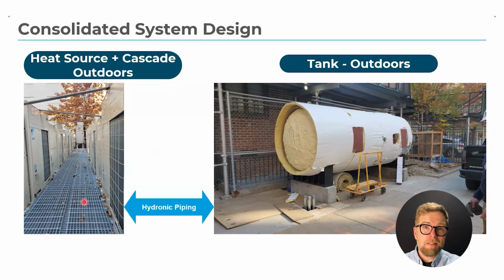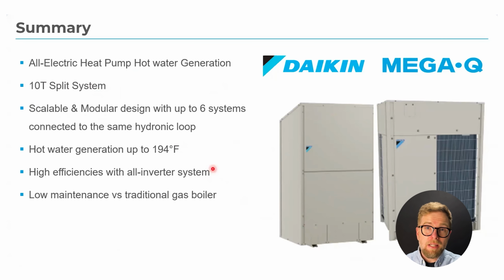Finally, if your end goal is domestic hot water for an apartment building or a hotel, it's easy to keep everything code compliant. You typically install a field-supplied secondary heat exchanger or an indirect storage tank, so the R134A loop never mixes with your potable water. That's it. 2 refrigerant loops, a smart controller, and a flexible installation that let you swap boilers and slash carbon emissions, all without sacrificing performance. So there you have it, Daikin MegaQ, a proven heat pump hot water solution that can help developers, contractors, and construction managers meet increasingly tough decarbonization targets without sacrificing performance.